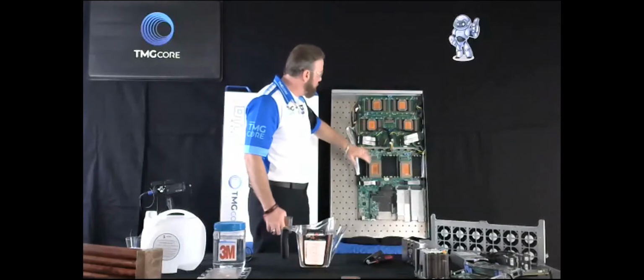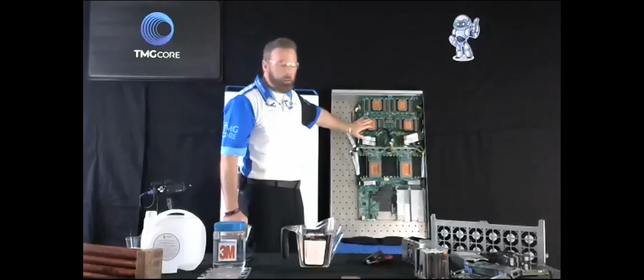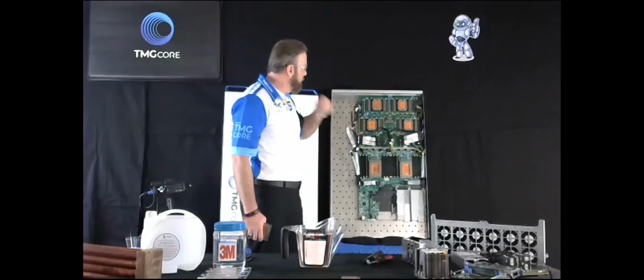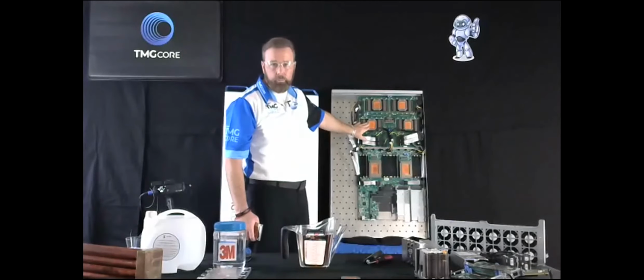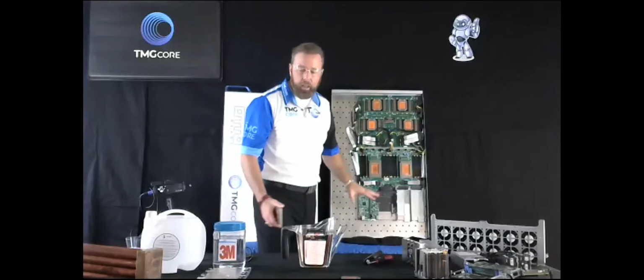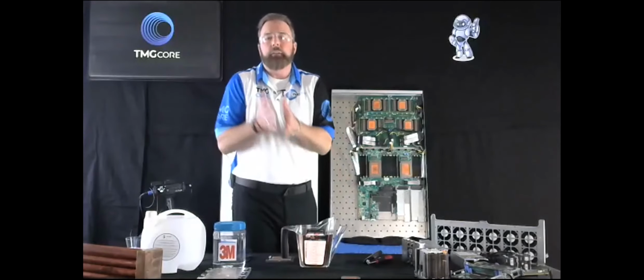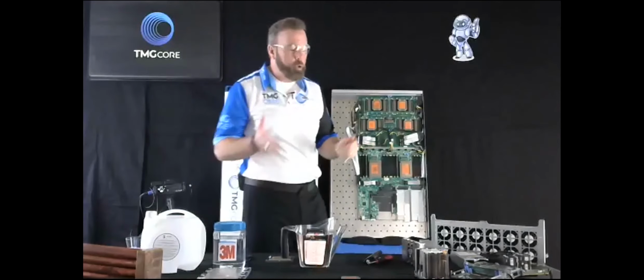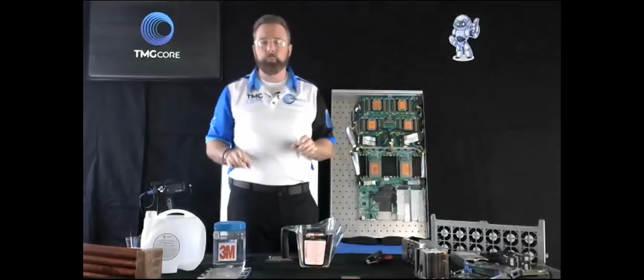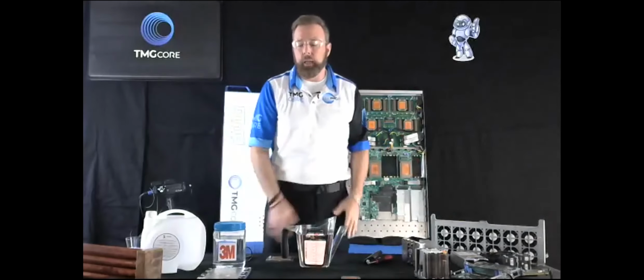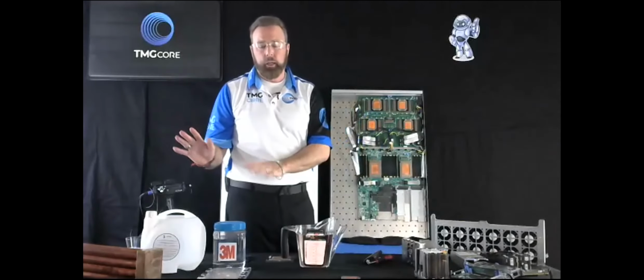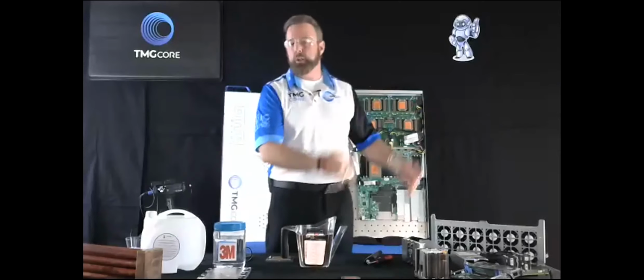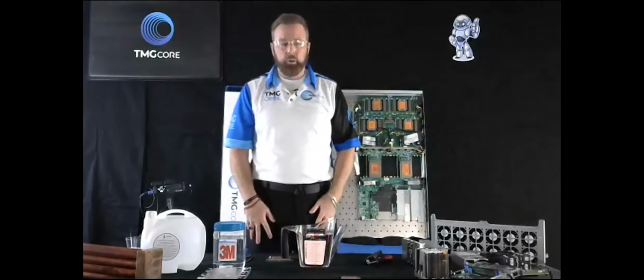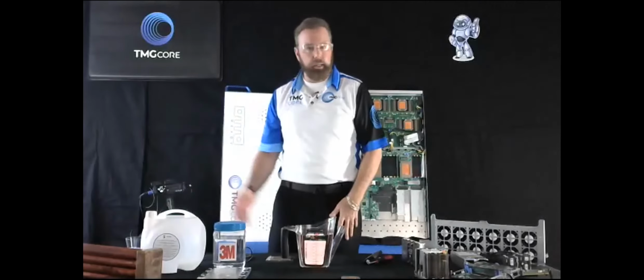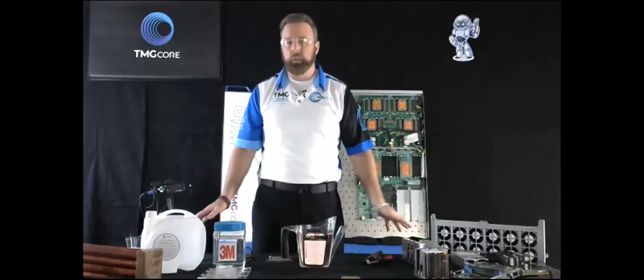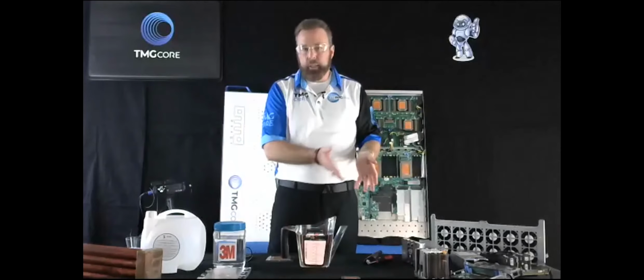So we're able to get close to 60 watts per cubic centimeter of heat transfer in some of these cases, which is incredible. But you have to have things really designed to make it valuable for two-phase immersion cooling. If you're looking at light loads, non-high performance computing, things that aren't extremely dense, then two-phase immersion cooling just isn't the right fit. You're better off going with a traditional rack, a rear door heat exchanger, water on chip, or even single phase, because single phase fluids are really inexpensive, but again you have limitations for density.